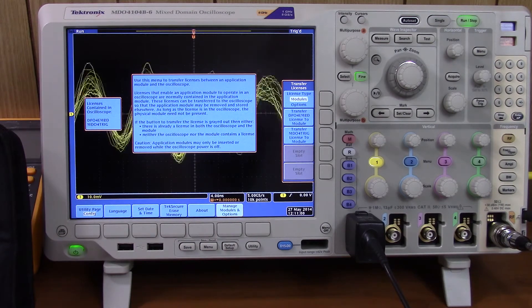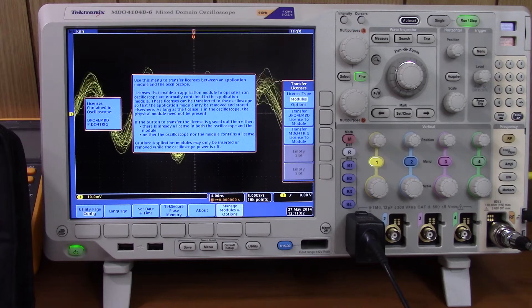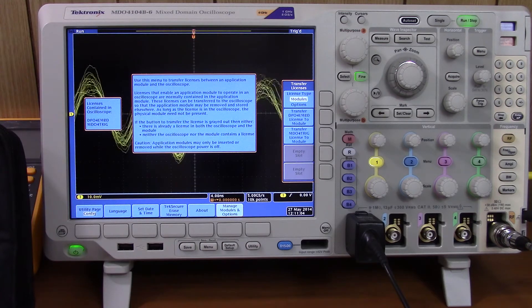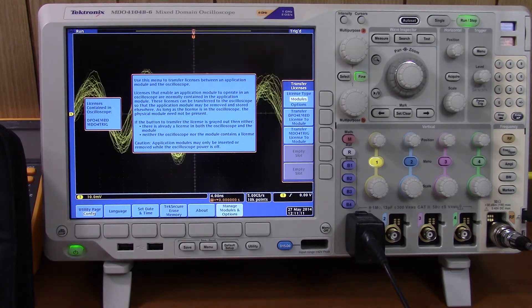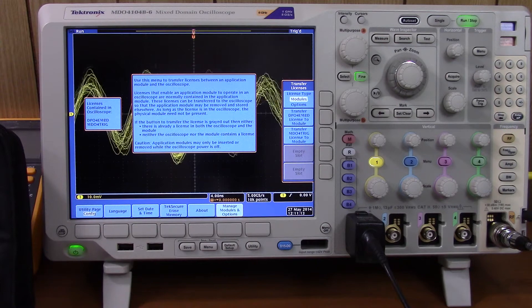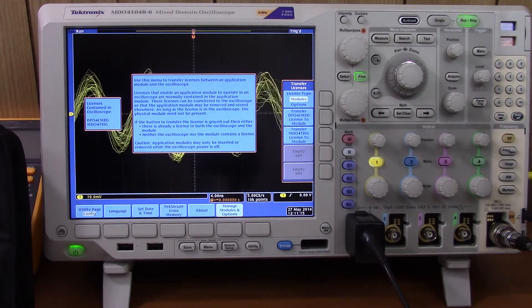Now, if I would shut the oscilloscope down and remove those option modules, the options will still be active. Now you might think, okay, well, it's easy then. In that case, I just buy one module and I install this on five oscilloscopes and I got this option on five different oscilloscopes and save the money. No, that doesn't work either. You won't outsmart Tektronix like that.